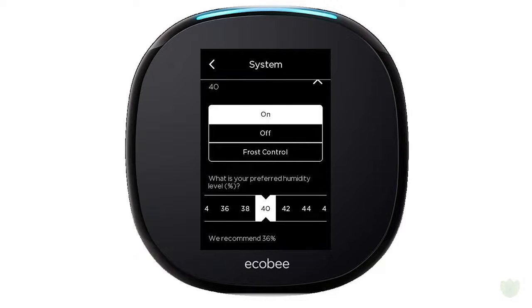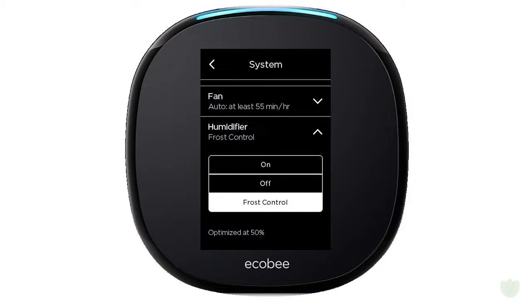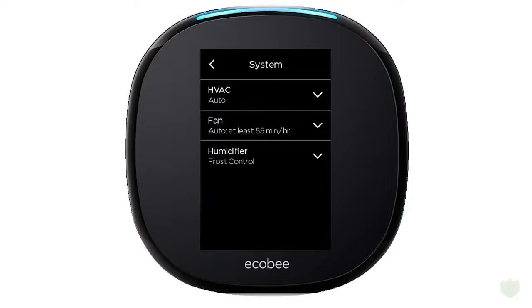If you don't want to have to worry about constantly adjusting that throughout the year, you can always use the frost control option. This option is going to look at the outdoor weather. It's going to look at the temperature. It's going to make those humidity adjustments automatically based on the outdoor temperature changing. So nice feature built in. We call it frost control. It's because it's going to prevent condensation building up on your windows, on the ceiling. Certain times of year we do hear stories from homeowners where it's actually raining in the house because the humidity is so high and it's very cold outside. So if you're using that frost control feature, you're going to avoid any problems like that.